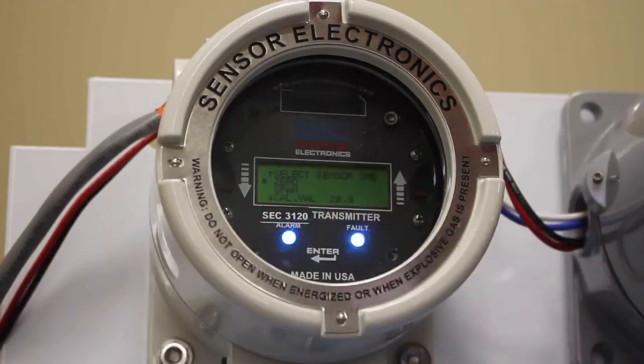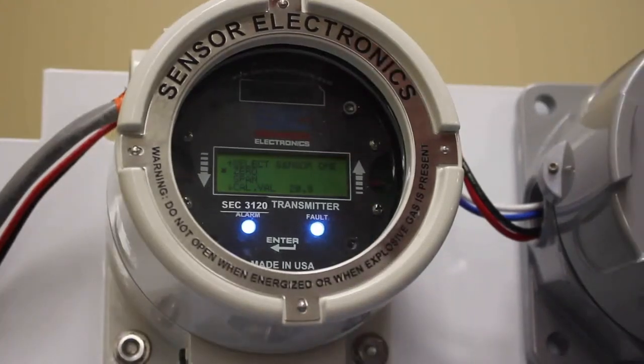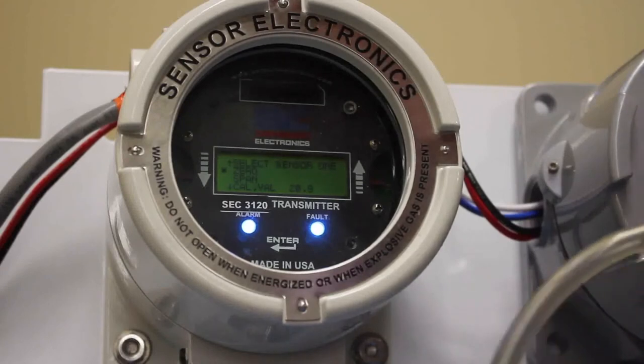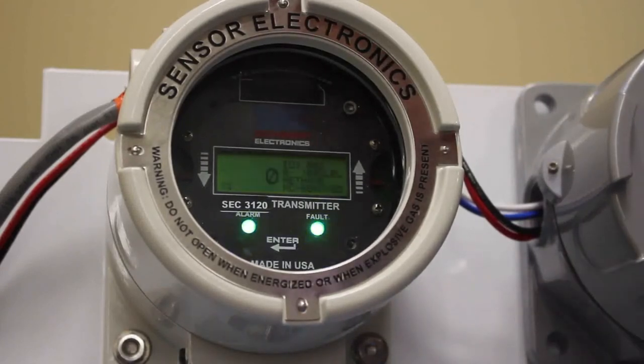And the first step in calibrating it is zeroing it. We have a calibration adapter that we screw onto the end of the sensor. This allows us to connect up to the calibration gas cylinders. And we thread that on. And then we have a flow regulator and tubing that we slide onto the barb fitting. And then we have the calibration gas cylinder.